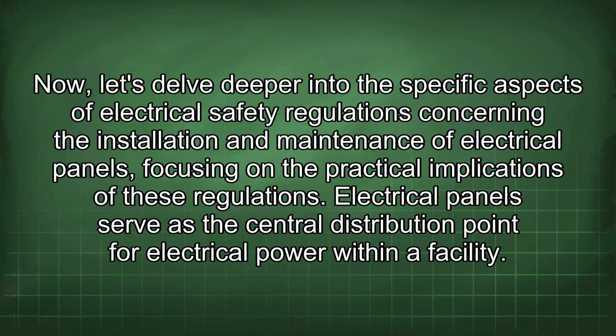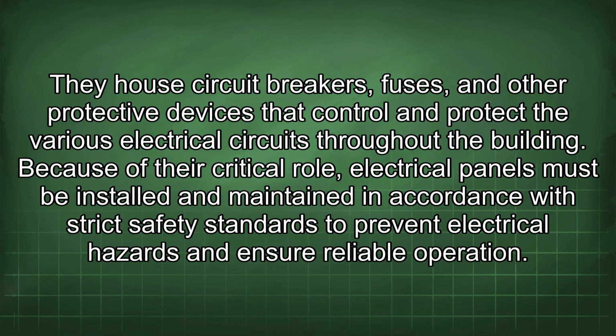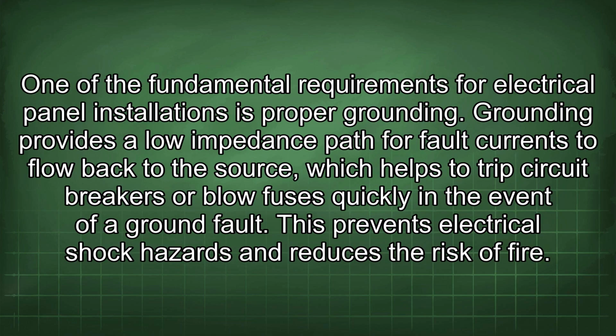Electrical panels serve as the central distribution point for electrical power within a facility. They house circuit breakers, fuses, and other protective devices that control and protect the various electrical circuits throughout the building. Because of their critical role, electrical panels must be installed and maintained in accordance with strict safety standards to prevent electrical hazards and ensure reliable operation. One of the fundamental requirements for electrical panel installations is proper grounding. Grounding provides a low impedance path for fault currents to flow back to the source, which helps to trip circuit breakers or blow fuses quickly in the event of a ground fault. This prevents electrical shock hazards and reduces the risk of fire.